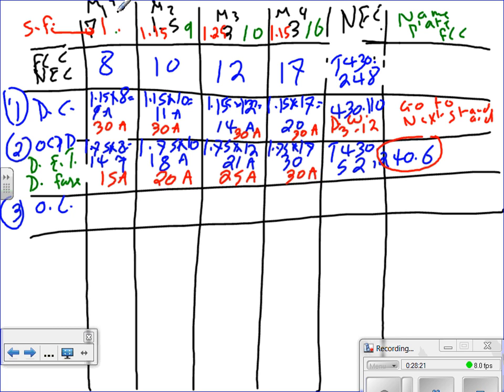Then you're going to go to, for the motor overload, 430.32. You're going to go to article 430.32 for the overload. If you read this article, it tells you the following: if the motor has a service factor of 1.15 or greater, you have to multiply the full load current on the nameplate by 1.25. In all other cases, it is 1.15.